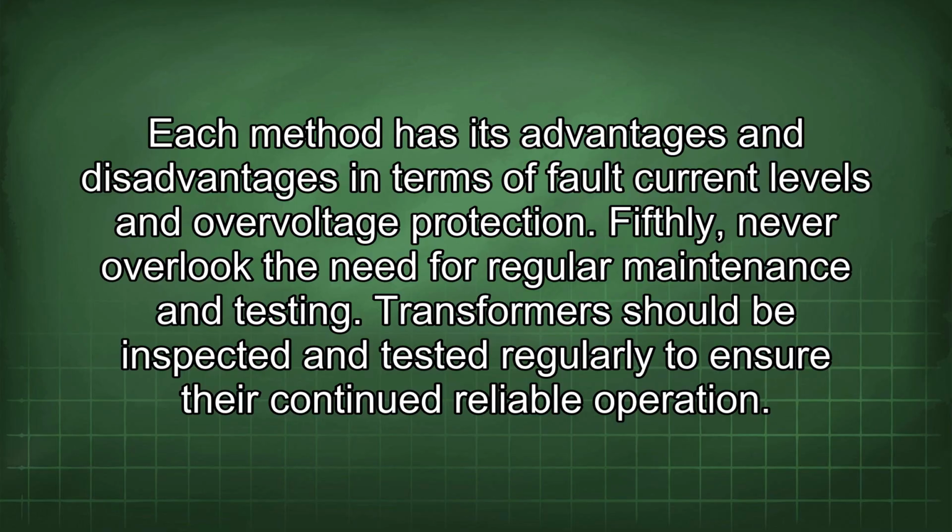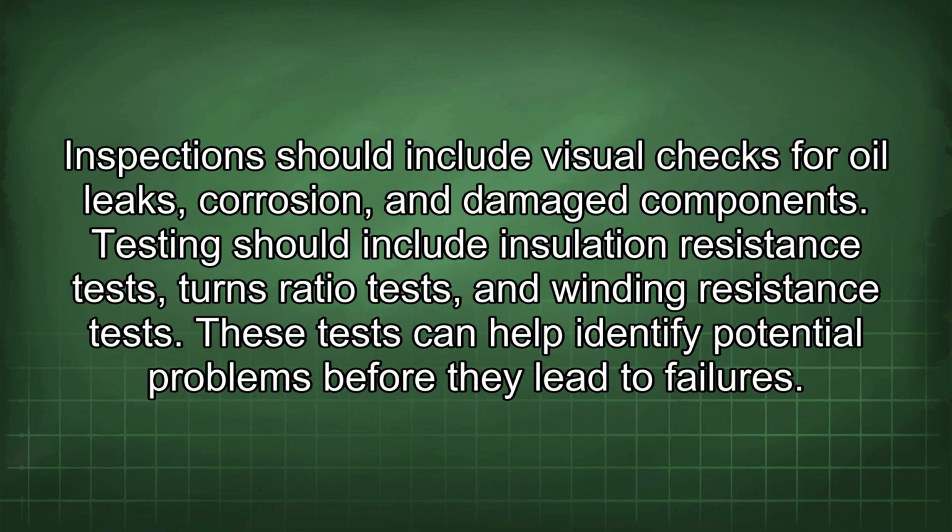Fifthly, never overlook the need for regular maintenance and testing. Transformers should be inspected and tested regularly to ensure their continued reliable operation. Inspections should include visual checks for oil leaks, corrosion, and damaged components. Testing should include insulation resistance tests, turns ratio tests, and winding resistance tests. These tests can help identify potential problems before they lead to failures.